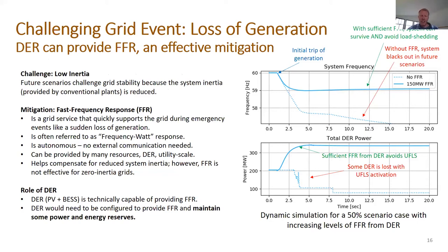One of the challenges is operating in low inertia. And what that means is, conventionally, synchronous machine power plants, so your coal, oil, and gas-fired power plants, all have rotating machinery, which provides inertia to the system. Essentially, that means that it slows the rate of the response of the system down when there's a sudden event that starts the grid moving. And so by having more inertia on the system, you have more time to respond. By having less inertia, or fewer of those conventional units online connected to the system, the grid starts moving faster and dynamic stability can be more challenging to maintain.